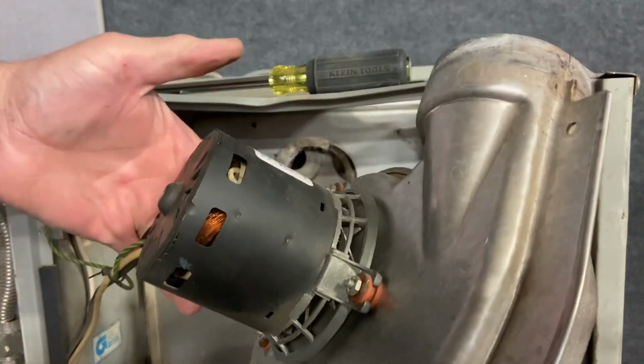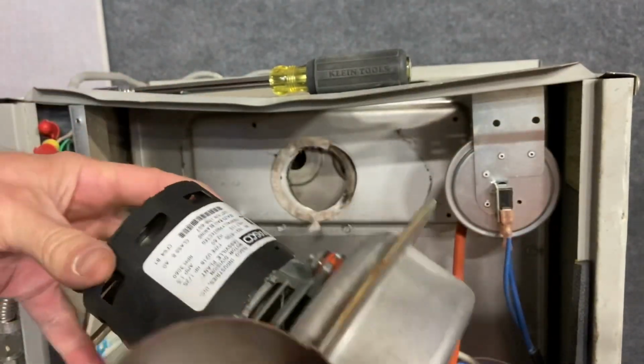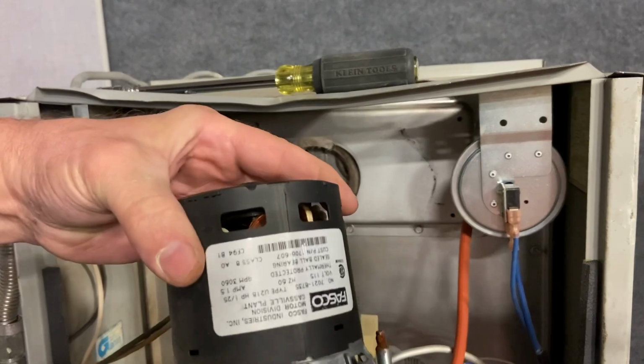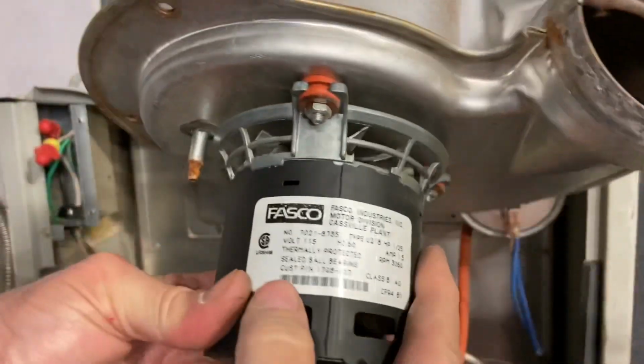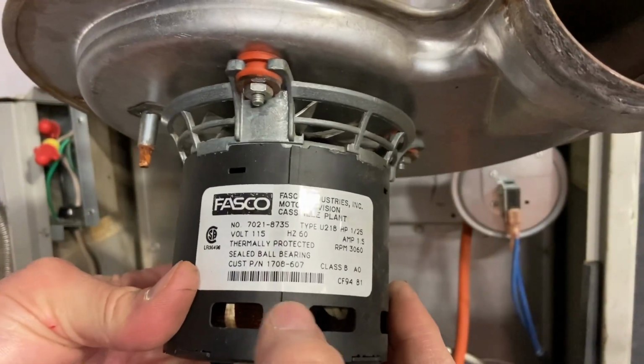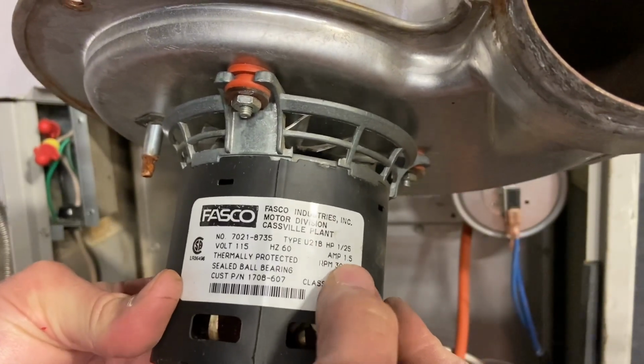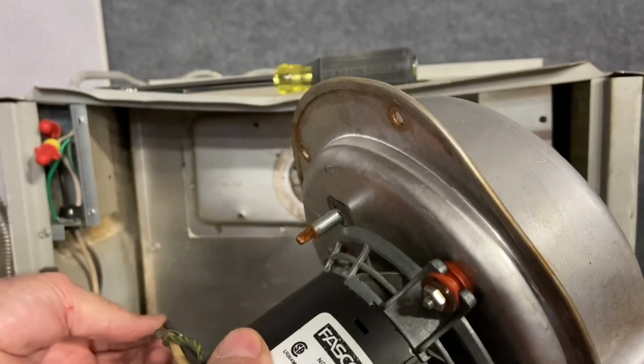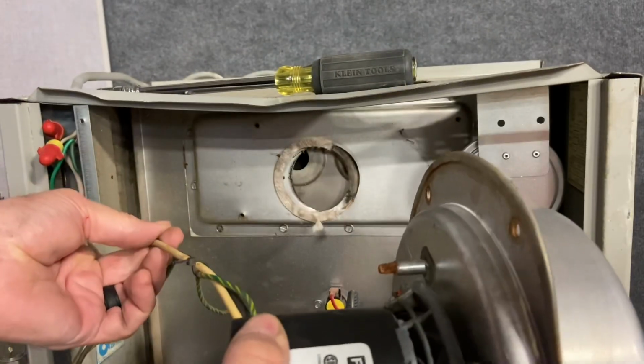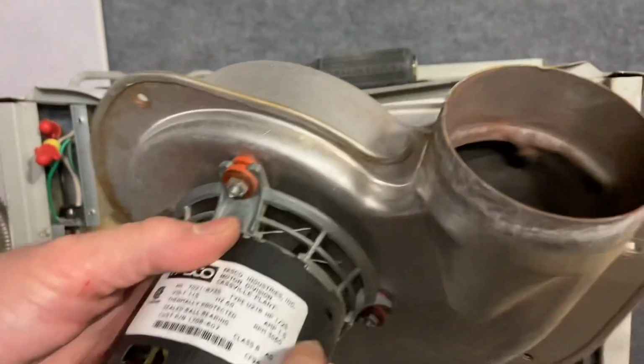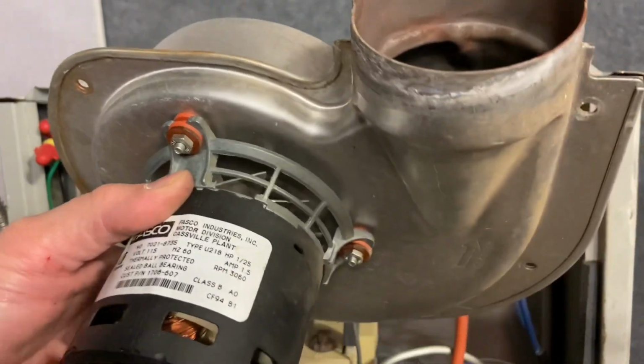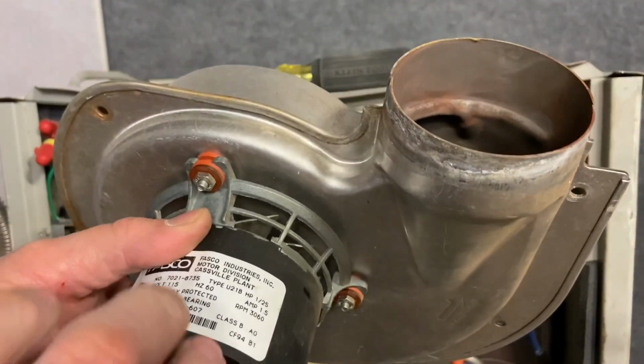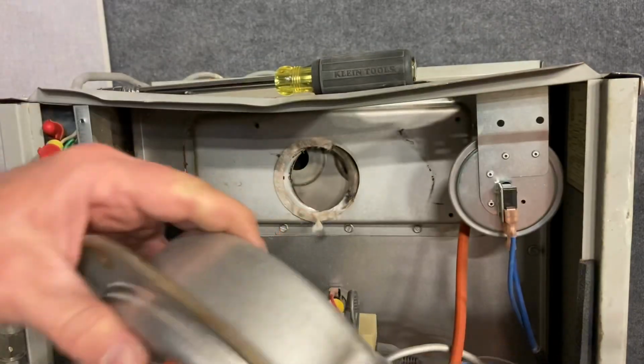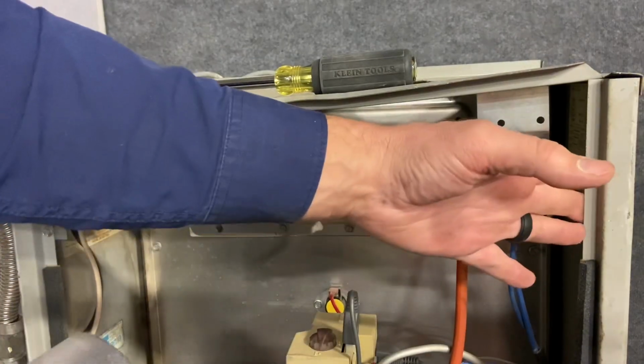So this is our inducer draft assembly. It's just a simple motor. There is no capacitor in this particular one. And we also have the tag on this motor. Some pretty important information here, mainly being the amp draw of this motor. It's rated for 1.5 amps. So what I do is I'd clamp my meter around one of these wires and check the amp draw while it's working. If it's pulling more than 1.5 amps, we know that we have some kind of an issue going on. Other than that, we replace these as an assembly by the model number and serial number on the unit.